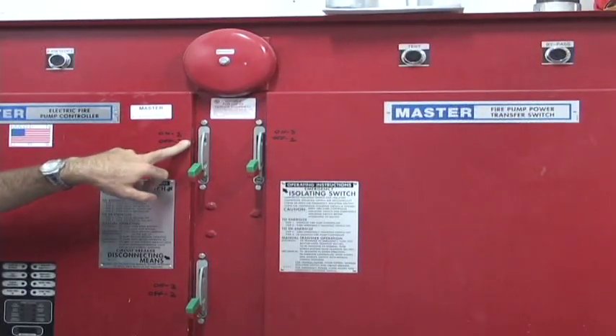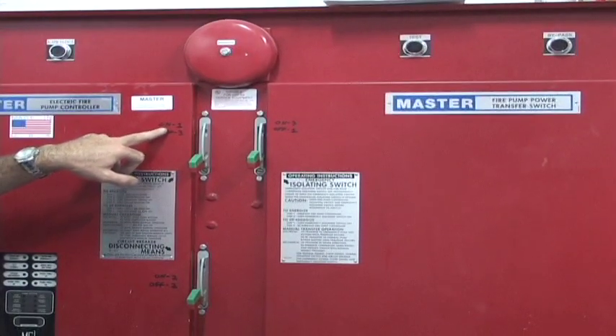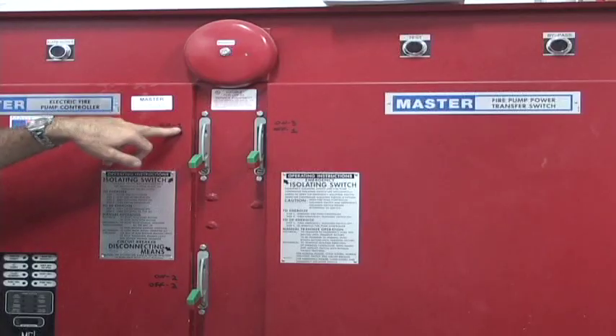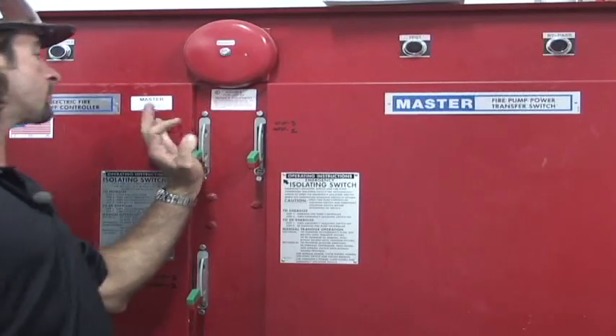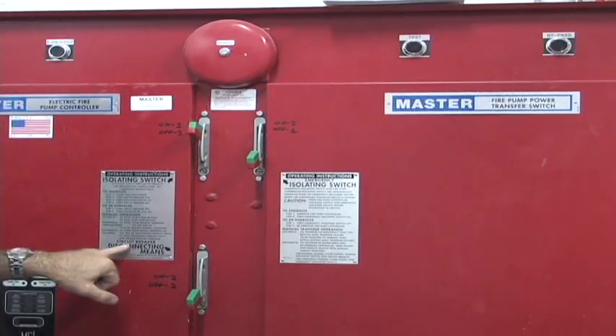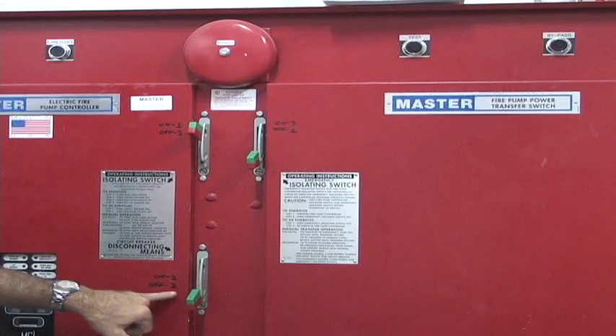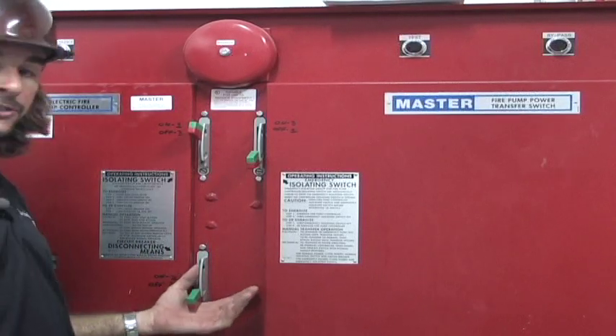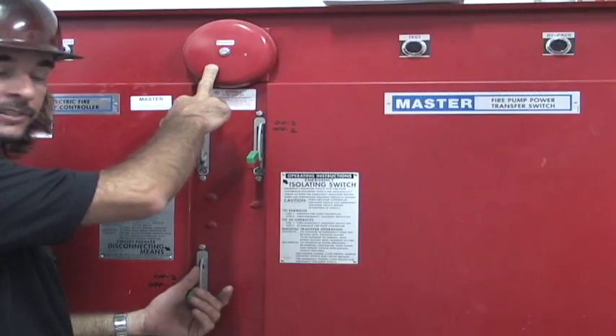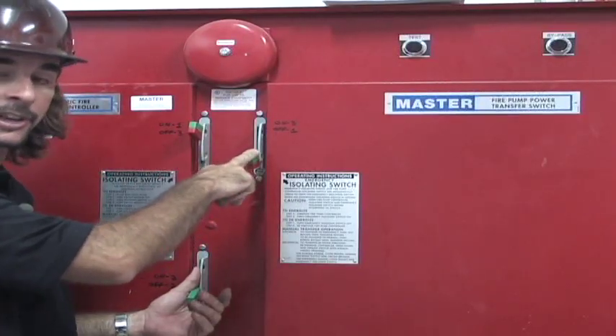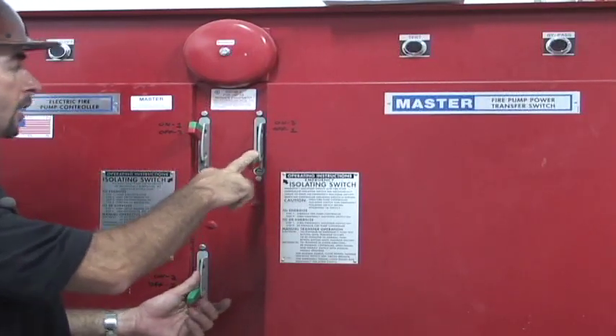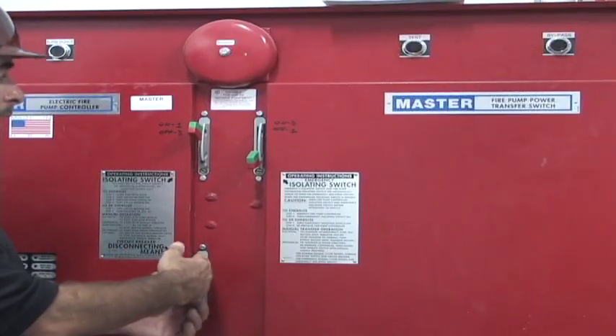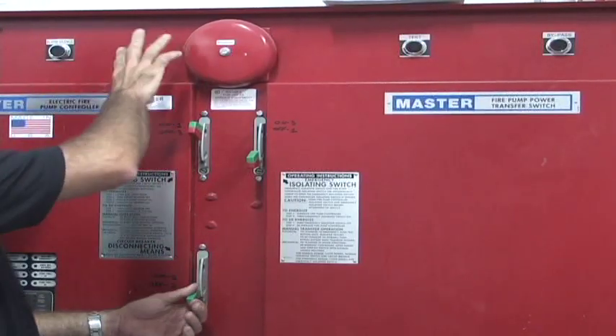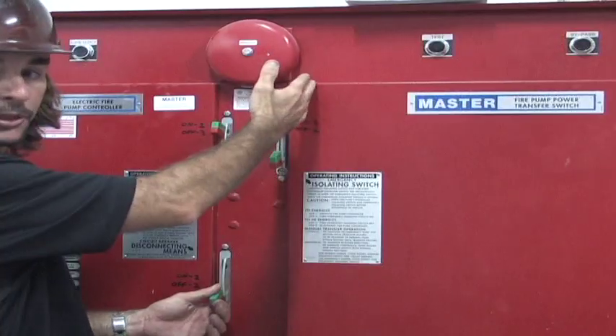As we fire this thing back up, we're going to go just counterclockwise. We're going to start with the isolating switch first. We're going to go to our circuit breaker disconnecting means, it's going to be our 2nd one. Once I throw this switch up, we're going to have the bell go off, which is going to tell us that our emergency isolating switch is in the off position. From the time we throw this 2nd one, we hit the alarm silence that'll stop our bell, and then we throw the 3rd switch up.